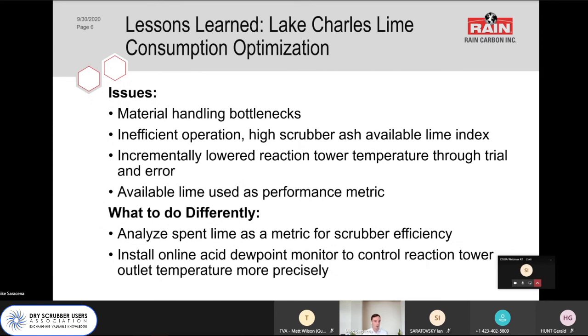So how the process went was we incrementally lowered the reaction tower temperature through trial and error while being conscientious of the available lime index and corrosion and trying to balance that really without any real-time feedback like an online acid dew point monitor would give you. So it was really an incremental trial and error based way to improve the system, which, maybe not necessarily the best way, but it certainly is the lowest capital cost way to improve the system, assuming you don't damage anything. So as I mentioned, we're using available lime index as our primary performance metric.